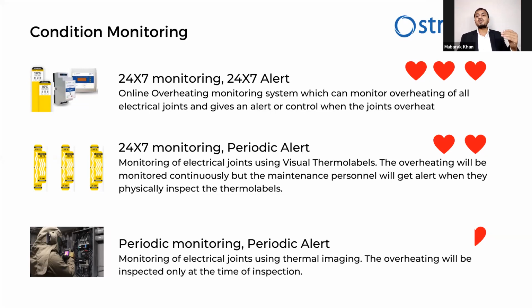That means monitoring of the electrical joints using thermolabels. Overheating will be monitored continuously, but the maintenance personnel will get alert only when they physically inspect the thermolabels. And the third one, through which people normally try to achieve the condition monitoring, but we don't get it actually, is thermography. Monitoring of electrical joints using thermal imaging, where the overheating will be inspected only at the time of inspection. For this method, I have given only half a heart. It means if somebody asks me to accept it, I will accept it only half-heartedly.